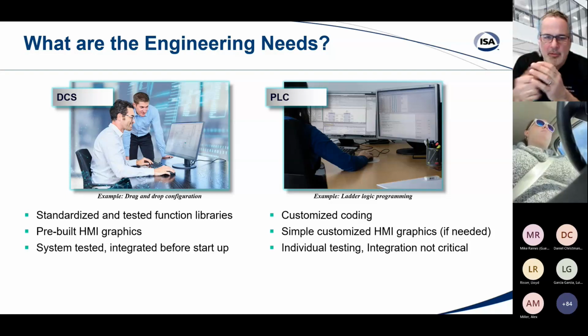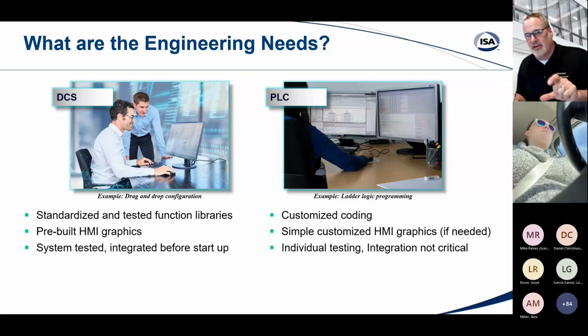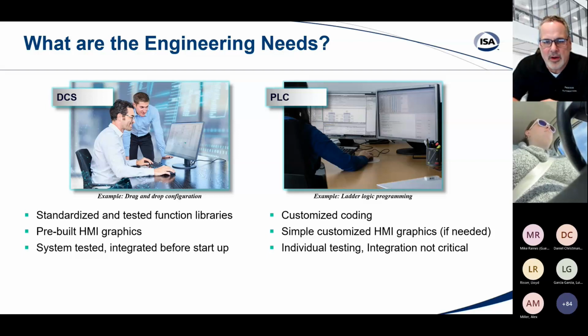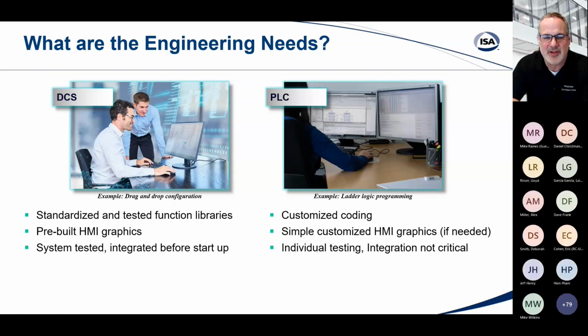We were comparing notes, and I was showing him this mid-select block that we had on the DCS side, where you can bring 3 transmitters in, and it automatically selects the mid signal. If one of the transmitters goes out, it readjusts, and it makes sure that it gives you the most confidence that you're getting the right process signal, process variable into the control system. Whereas on the PLC side, he goes, yeah, we can do that too, but not out of the box. So they could build that logic, they could build that functionality, but it's all going to be customized.